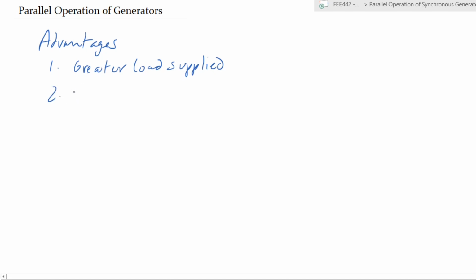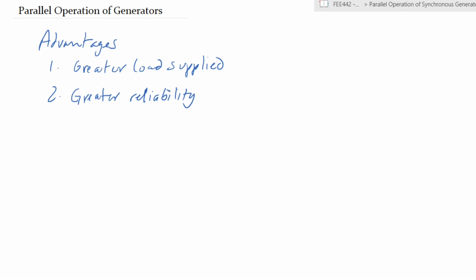Secondly, you can have greater reliability of the system. This means that if any one generator would fail, you are likely to be able to still manage to supply at least some of the load because of the other generators that are connected. Whereas if you only have one generator, you'll only be able to supply as long as that generator is functional. If it goes down or if it has any issue, you would not be able to supply the load.